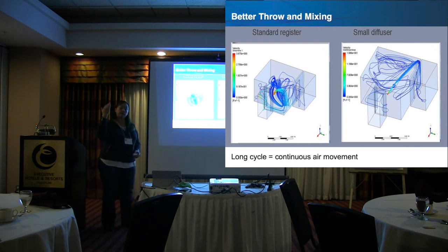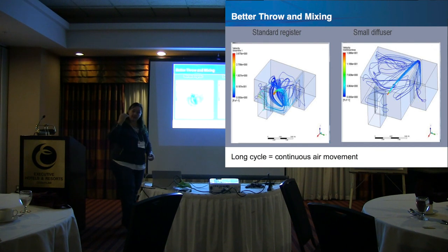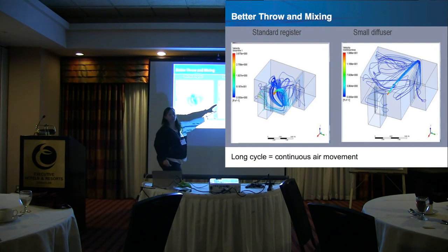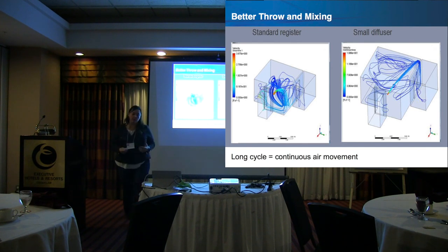The diffusers are 6 inches from the ceiling. We're getting 9 feet of throw. The air sticks to the ceiling as long as it can. It's called the Coanda effect. So it will stick to the ceiling as long as it can. So 3 feet of throw versus 9 feet of throw. So much better mix and distribution.